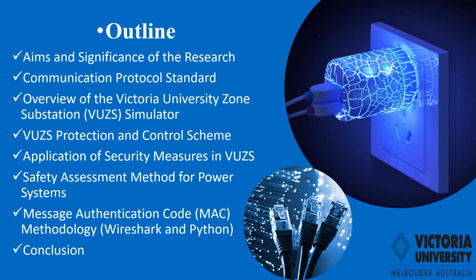The outline of this presentation includes the aims and significance of the research, the different types of communication protocol standards, the overview of the Victoria University Zone Substation, the VUZS simulator, the VUZS protection and control scheme for the IEC 61850, that's a communication network, application of security measures in Victoria University Zone Substation, including IEC 62351, that's the data and communication security, the safety assessment method for power systems using the GOOSE, MMS, and SV, the message authentication code methodology using Wireshark and Python, and the last one is the conclusion.